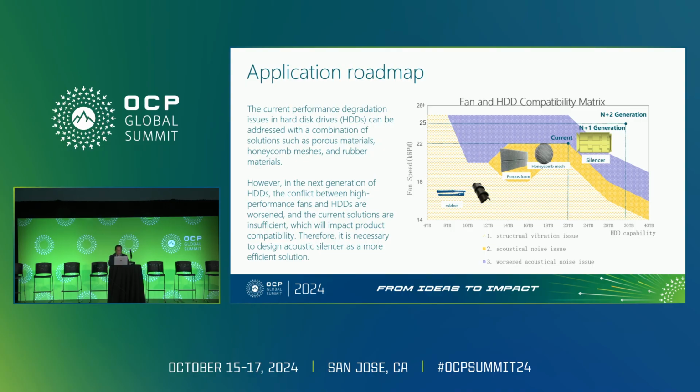The silencer cavities are designed to target the frequencies to which the HDD are most susceptible, significantly improving HDD IOPS performance to meet or exceed corporation specifications. By doing so, the silencer ensures a stable and reliable operation of HDD, even in high-density server environments.